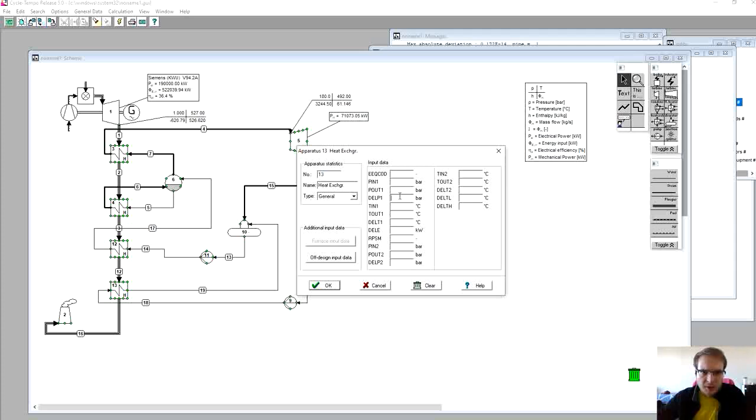Now specifying the heat exchanger, again we need to specify the pressure drops or pressure differences. And now, since we have fixed mass flow rates on both sides, it's not entirely feasible to specify the high or low temperature pinch points or temperature differences. But we know that the deaerator is at 105 degrees C, so let's specify that: we want to heat up our water, stream number 1, the primary side, to 100 degrees C, just below the saturation level. And EEQ code number 2.